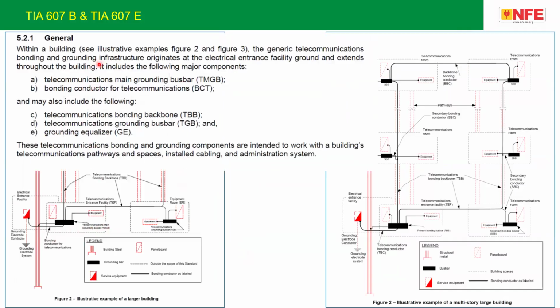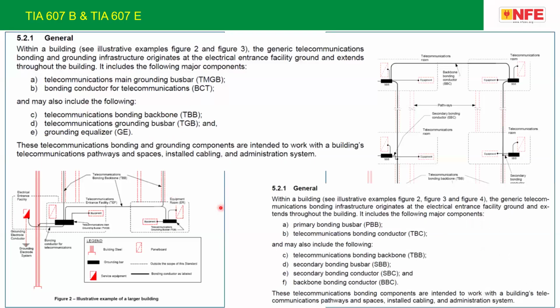Now, if you look at the pictures, I am showing two pictures, the left one from 607 B, the right one from 607 E. If you look at some of the wordings used, for example here, the old nomenclature used in the standard was 5.2.1 within a building, telecommunication main grounding bar, bonding conductor, telecommunication bonding backbone. The old nomenclature is being replaced with new names in 607 E. The telecommunication main grounding bar has been changed to primary bonding bar. Telecommunication bonding conductor for telecommunication is changed to TBC.